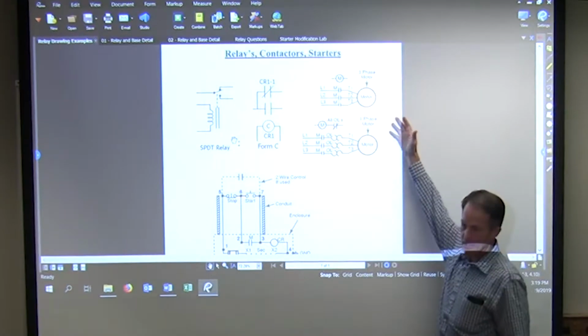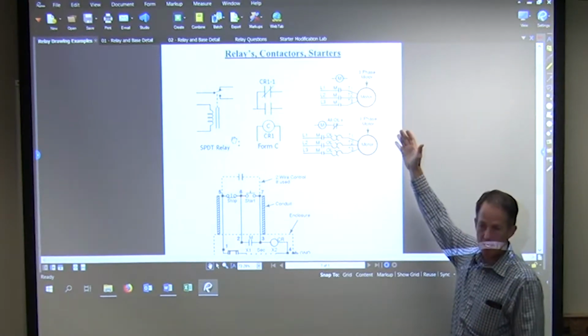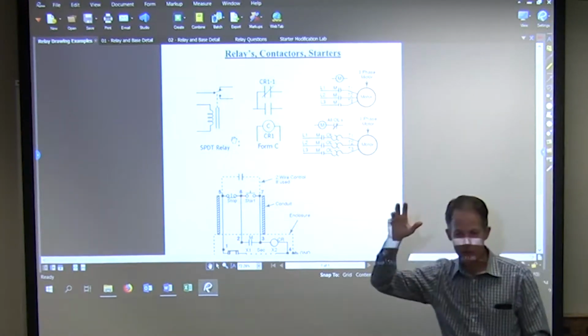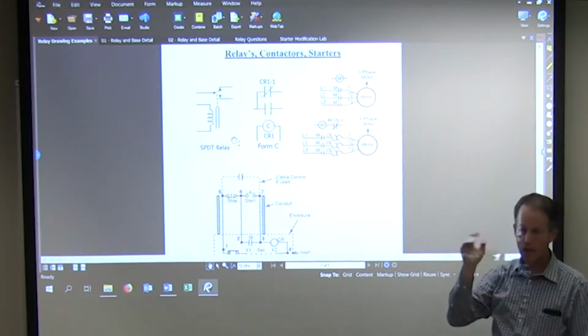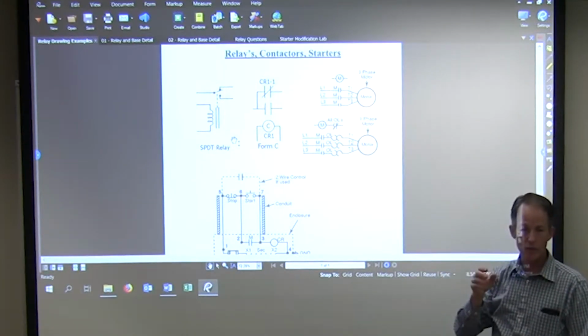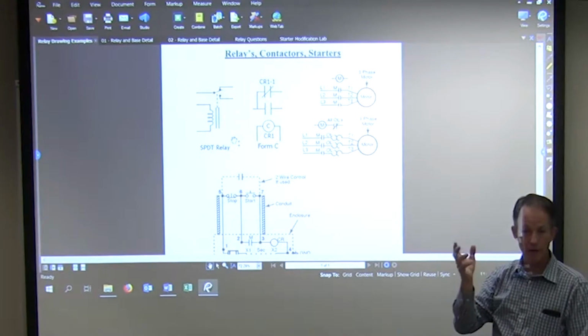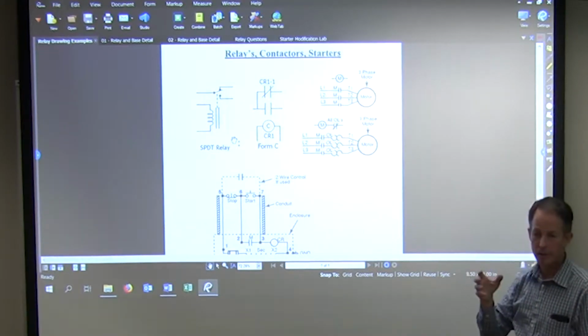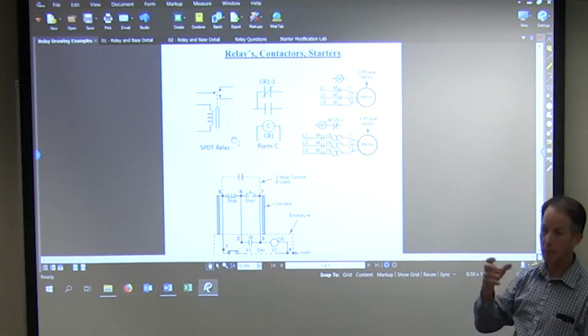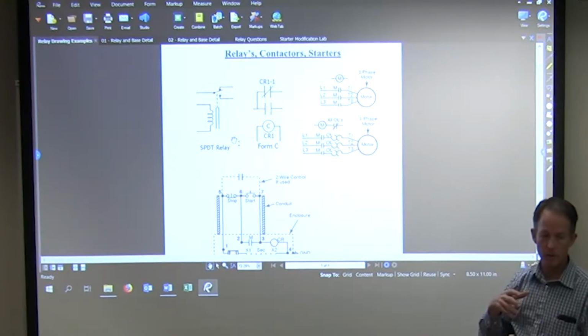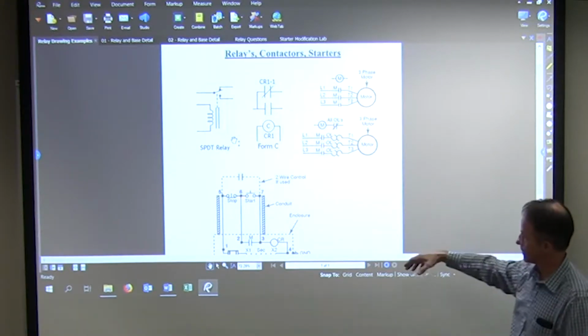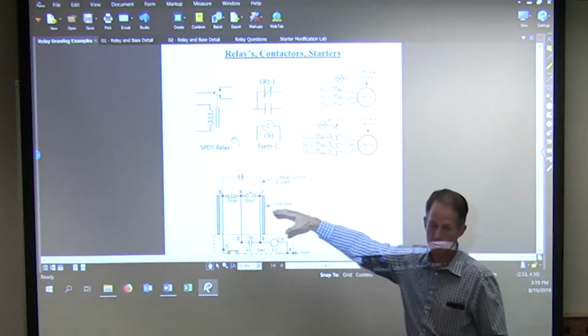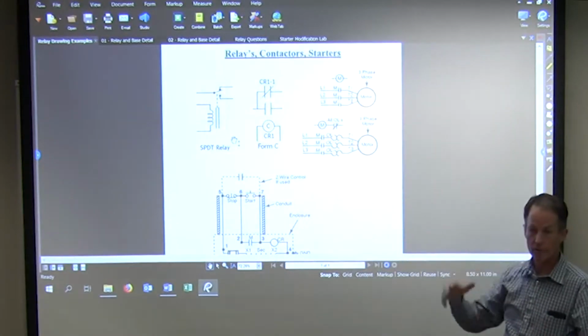We've got a couple things up here in the upper right, that motor contactor and starter. A contactor typically is just a way of turning a motor on and off. A starter typically has a few other components in there to protect the motor. And we're going to look at this piece down here. We'll scroll down to it in a minute. It's a little more involved starter.